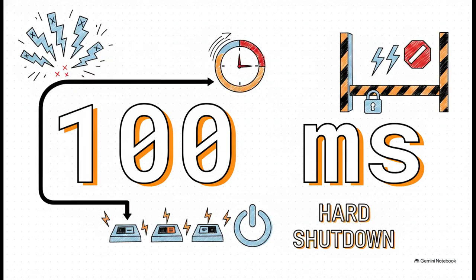But what if multiple channels fail all at once? That points to a massive, catastrophic physical shear. In that case, the system absolutely does not wait around. It gets a mere 100 milliseconds. That is the strict fault-tolerant time interval limit to execute a hard shutdown, instantly triggering the relays to physically isolate the high voltage before disaster strikes.